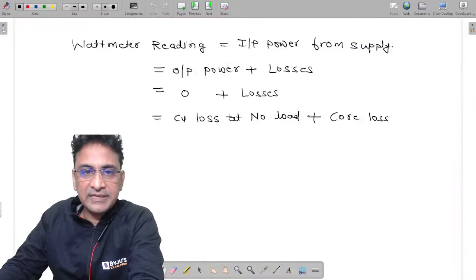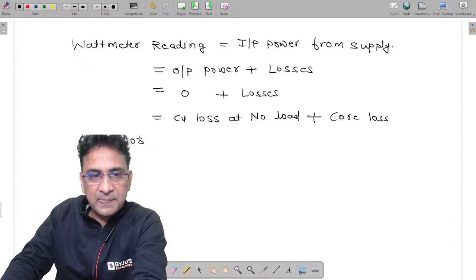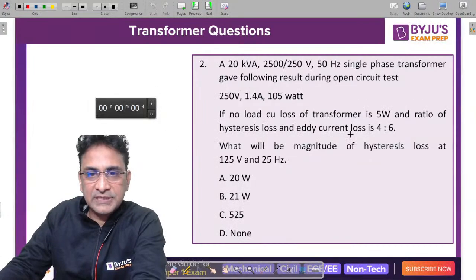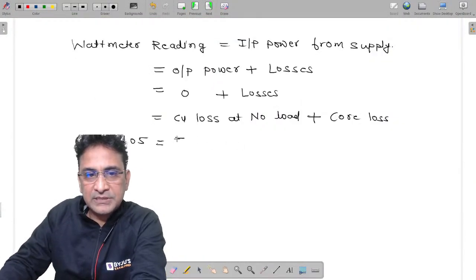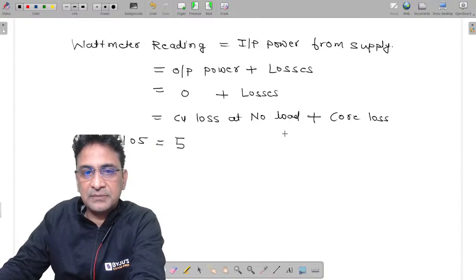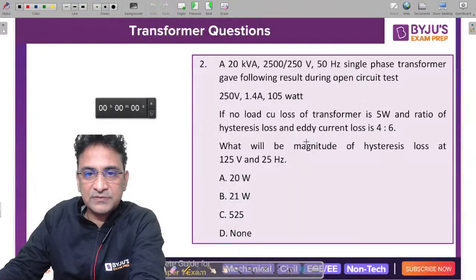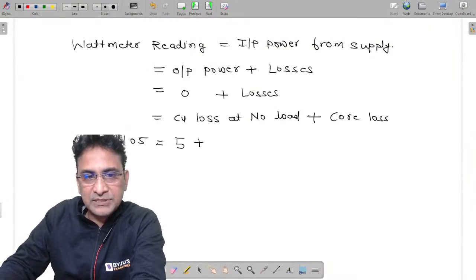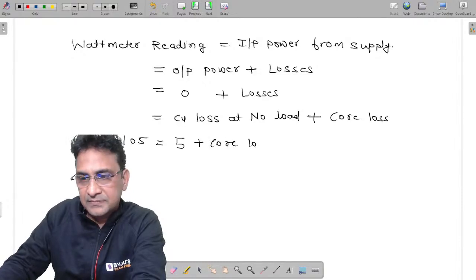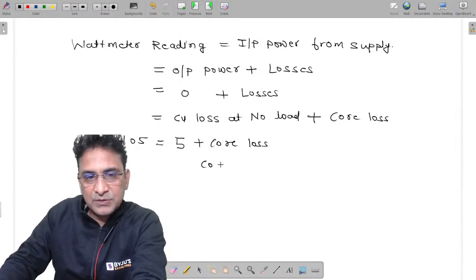So the total reading is 105 watt and the copper loss at no load is 5 watt. The copper loss takes place only on the primary side because no current flows on the secondary side. So the overall core loss becomes 100 watt.